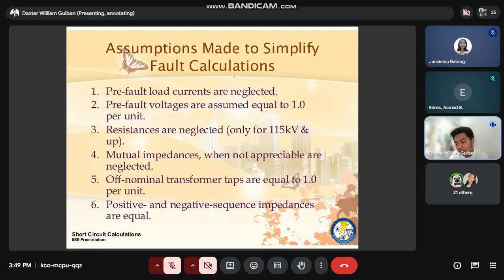Then the pre-fault voltage or katong EA1 are assumed to be equal to 1.0 per unit. And most of cases, resistances are neglected. So that's why your impedances will have a reactance value only. And mutual impedance when not appreciable are neglected. Then off nominal transformer taps are usually set by 1.0 per unit. And in most cases, positive and negative sequence impedance are all equal. Mana nga mga assumptions. Then you can have your short circuit analysis.